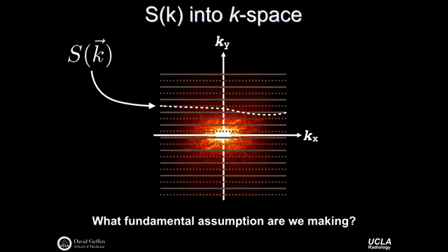So when our gradients don't do exactly what we want them to, we know less precisely what K points we acquired. And as a consequence, our K points will not be assigned to their correct K space position. And you'll end up with a number of different kinds of artifacts, usually relatively subtle for the specific thing I'm talking about. But the point is that gradient imperfections will bring you through a different part of K-space than was your target.